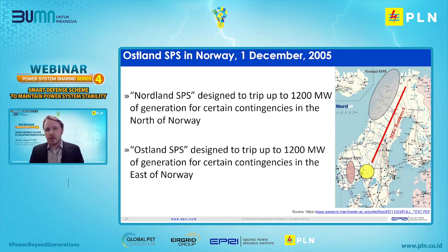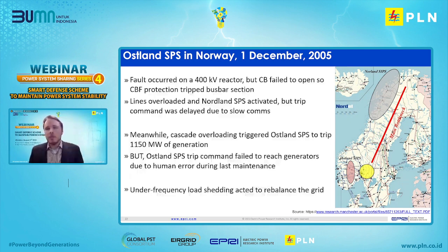However, on the 1st of December in 2005, a busbar 400 kV reactor suffered a fault and a breaker failed to open, so the circuit breaker fail protection tripped the busbar section. This caused line overloading and the north SPS to activate, but due to very slow communication systems, the command did not reach the generators in time.